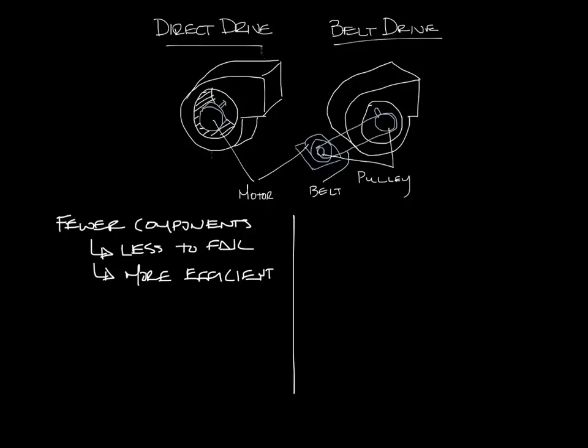On the downside, the fan can only turn the same speed as the motor. So to increase or reduce the airflow, you have to change the speed of the fan. This is exactly what you're doing when you use an SCR or a PWM on a fan powered terminal unit.